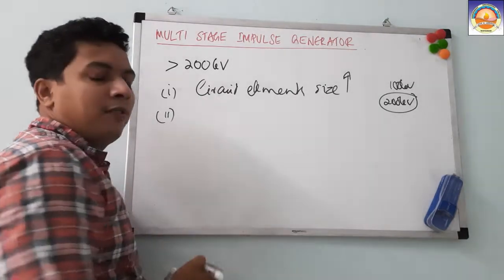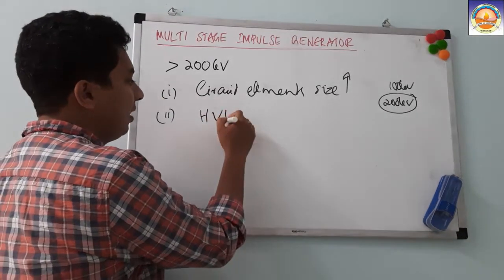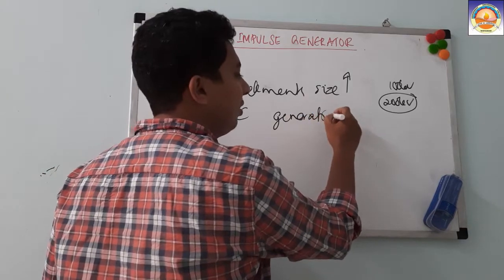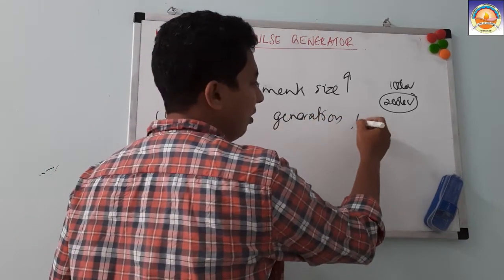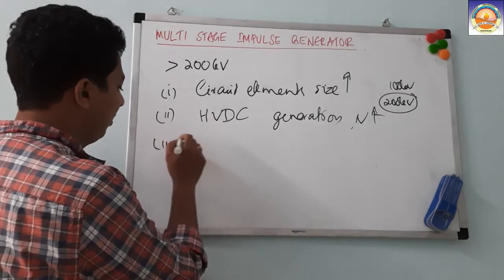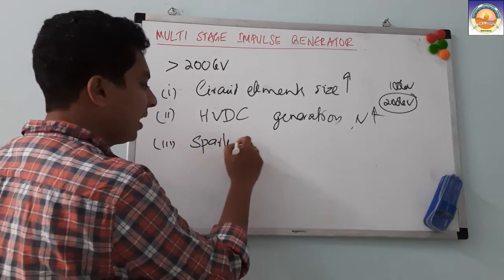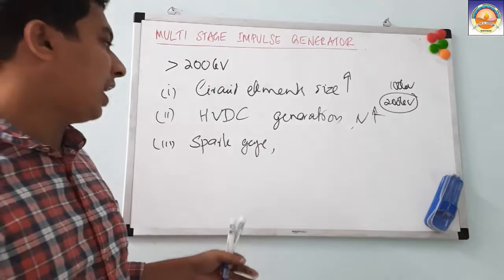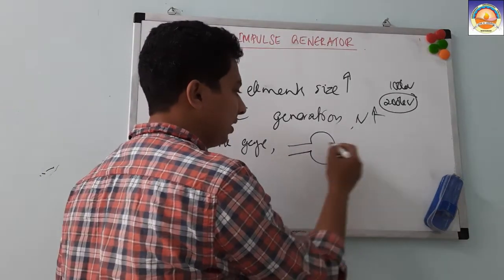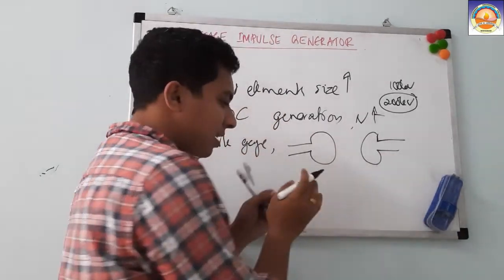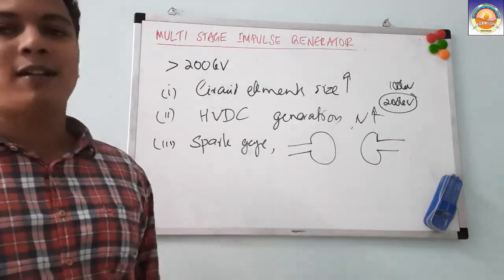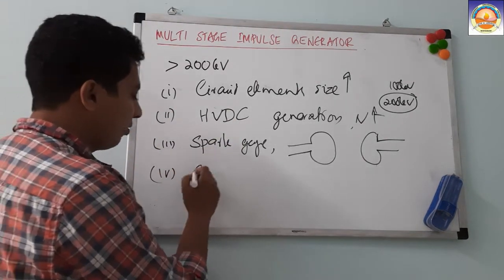Another problem is that we need high voltage DC, and it is hard to generate — high voltage DC generation itself becomes a problem as voltage increases. The third problem is spark gaps: for very high voltages like 1000 kV, the spark gap is not reliable. For 100 kV it is reliable, but at 1000 kV it will not be reliable.